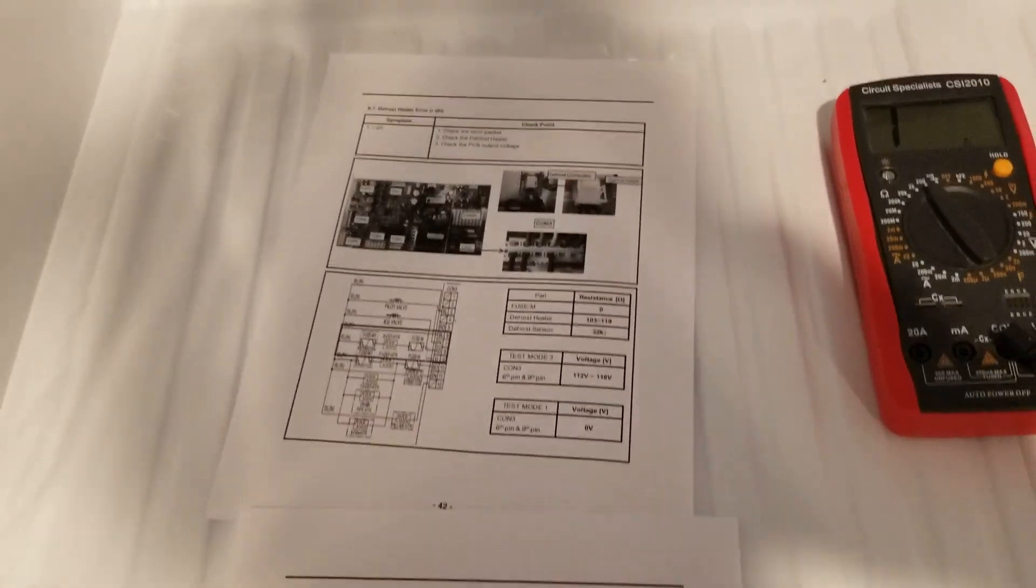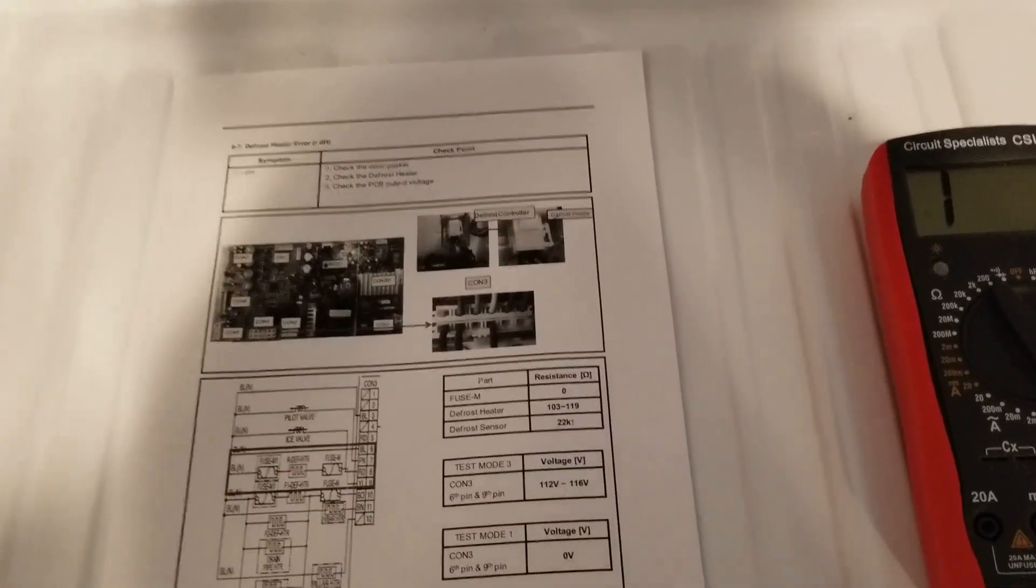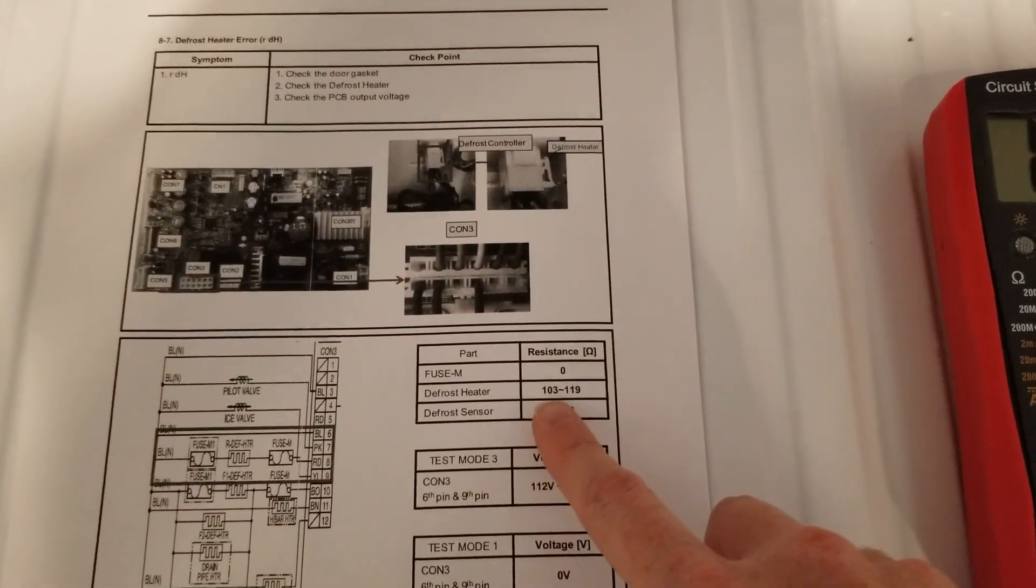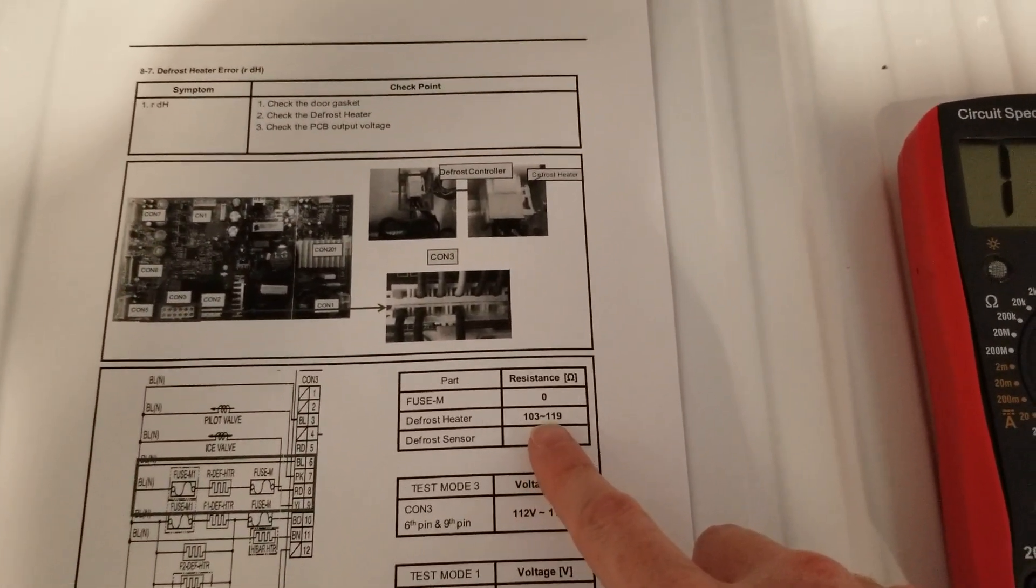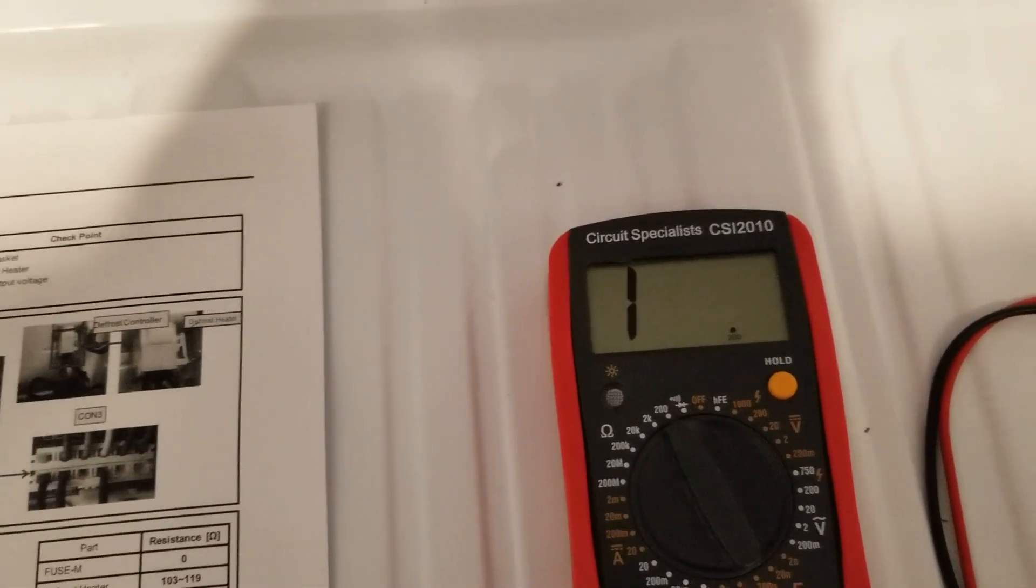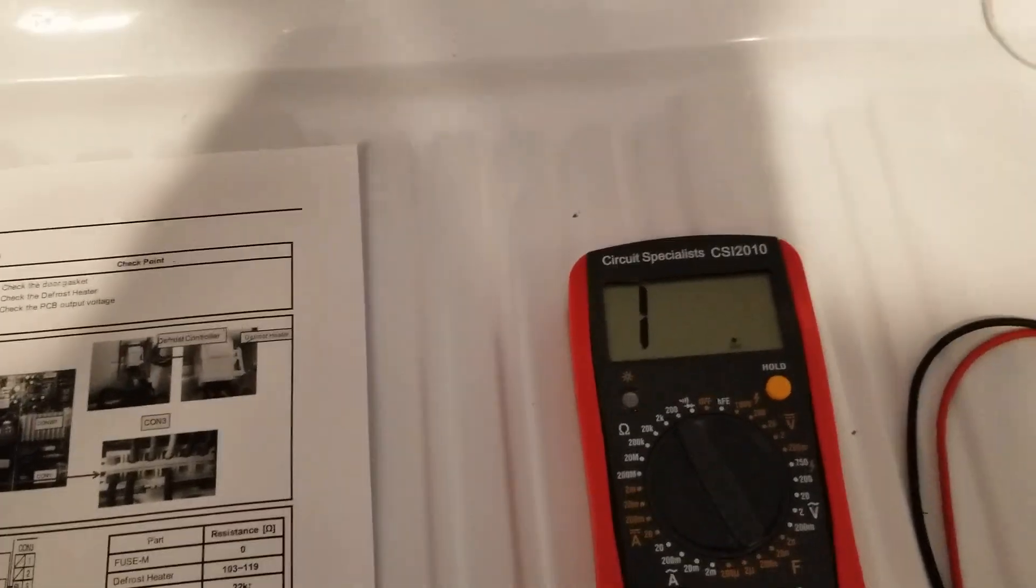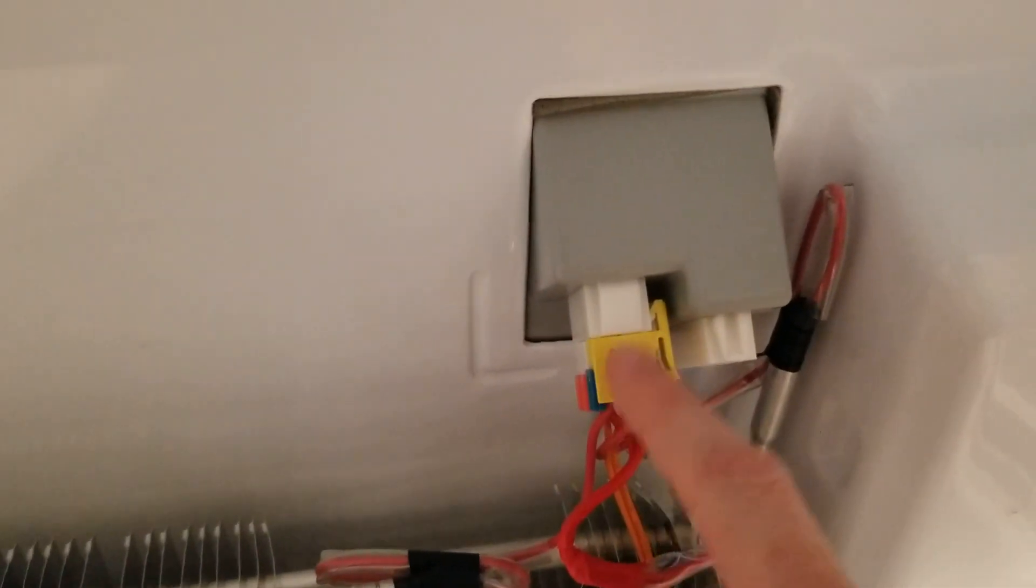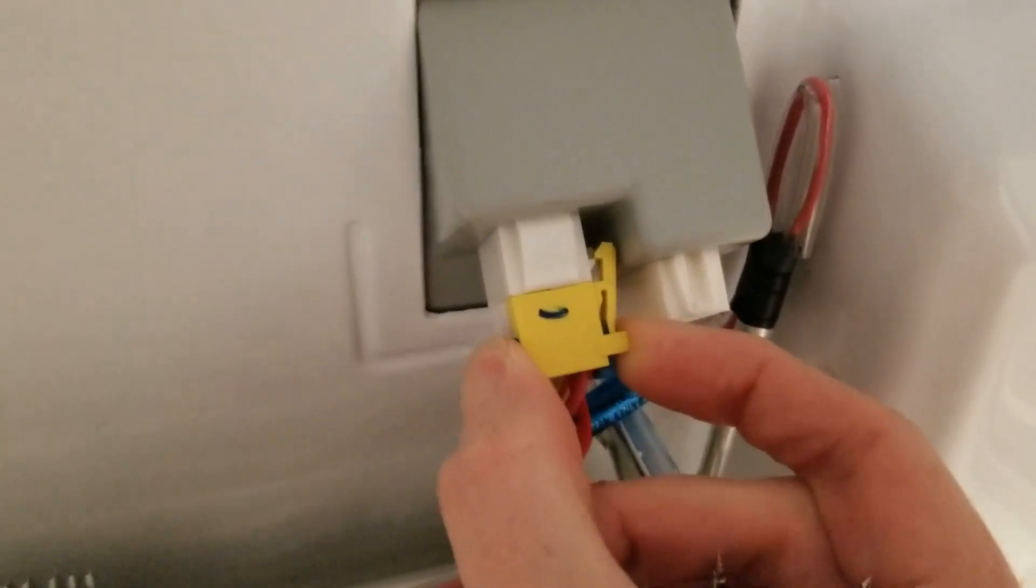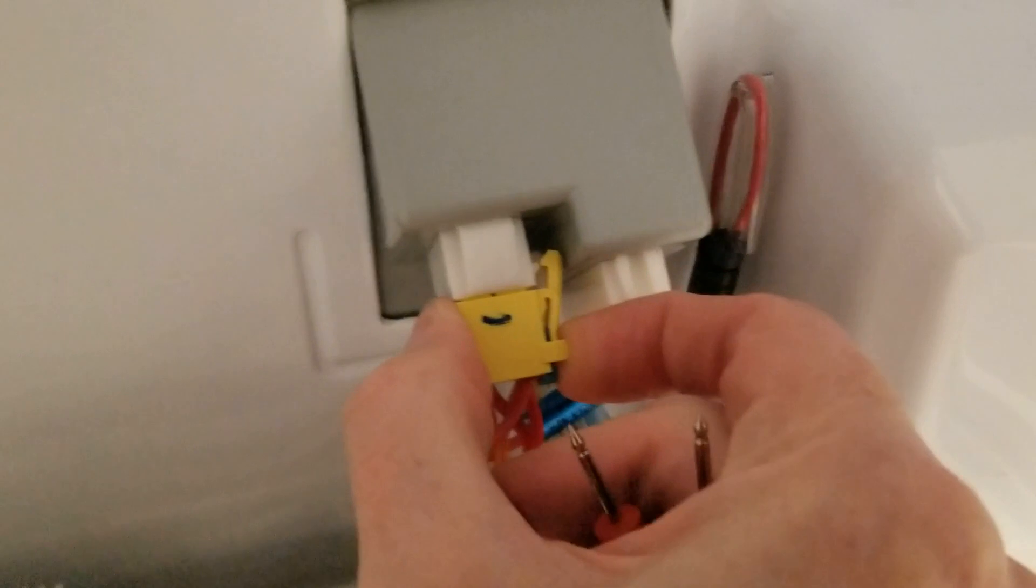First thing I'm gonna check is the defrost heater, which should be between 103 and 119 ohms. I have an ohm meter here set to 200 as its max value. The heater should be this first top yellow one. This is actually two pieces here.